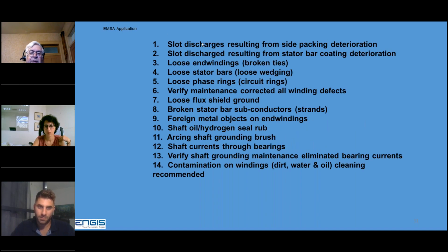For generators, similar things: slot discharges, which are a constant problem, loose end windings, loose wedging. Now, on this, EMSA will not detect loose wedges. It will detect loose stator bars, the 2-load test, for example. But you have to have loose wedges to have loose bars. Phase rings or circuit rings loose and moving around. Again, the 2-load test is very good with that. Verify the problems were fixed or not fixed.